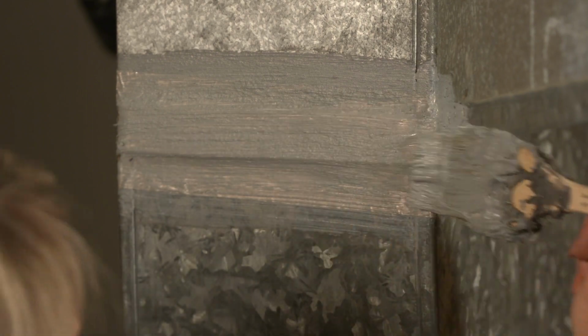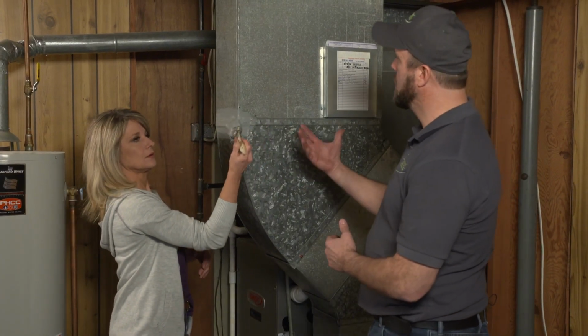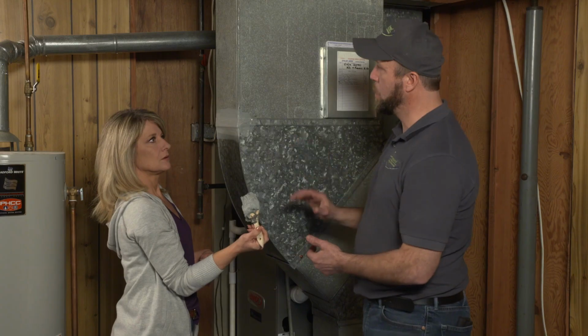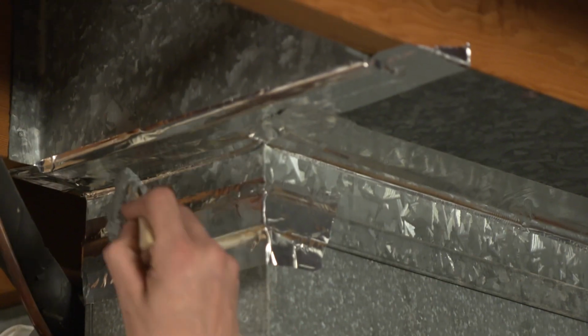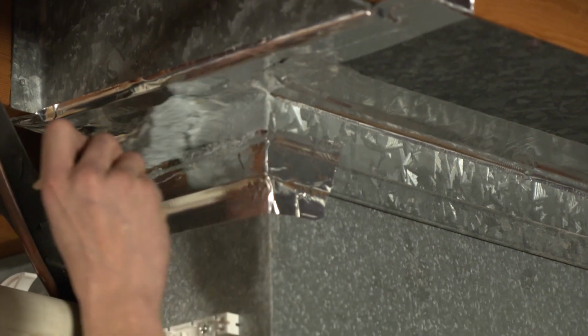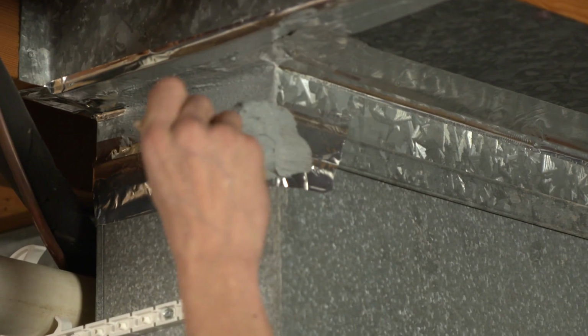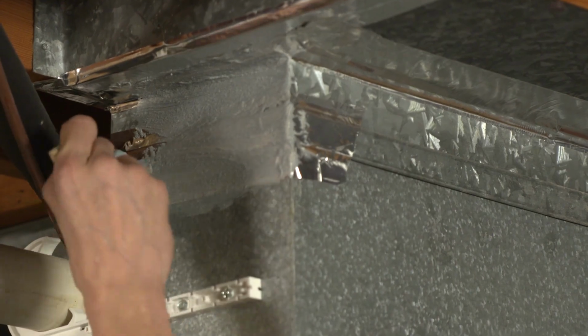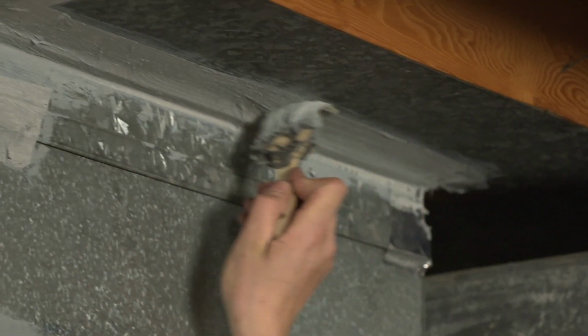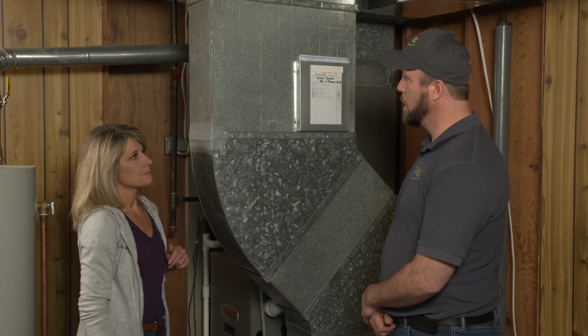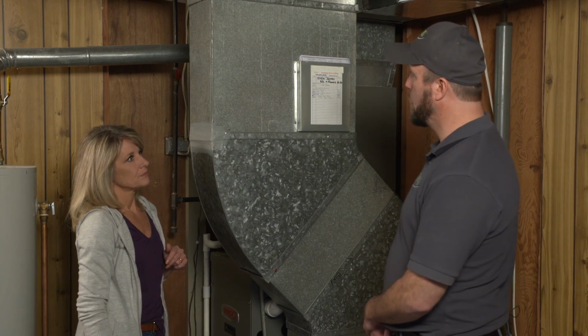Perfect. How's that? That looks great. The benefit of the mastic on top is that the tape can break down over time due to heat and temperature changes inside of the ductwork, but the mastic is a permanent solution to keep that ductwork sealed. It probably protects the glue to some degree too and holds everything in place. It does a fantastic job. That is the solution to making sure we don't have any further leaks in that area.